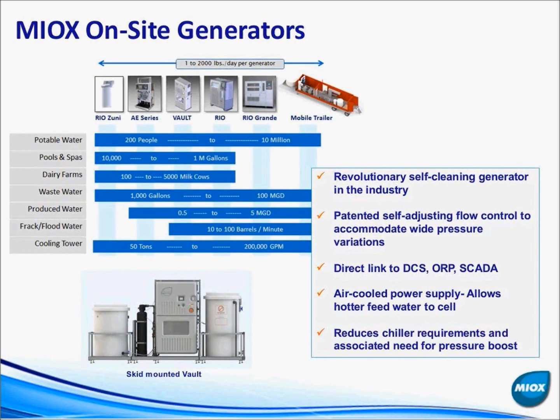We manufacture a huge variety of equipment — from one pound per day (about half a kilogram per day) of free available chlorine all the way up to thousands of pounds per day. All systems are rated in equivalent free available chlorine, so if you're currently using a hundred pounds a day of chlorine gas, you can find the matching unit on our data sheets. Even our thousand-pound-per-day units have a very compact footprint — roughly the size of two refrigerators sitting side by side.